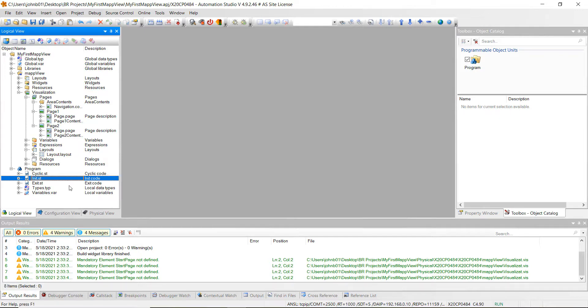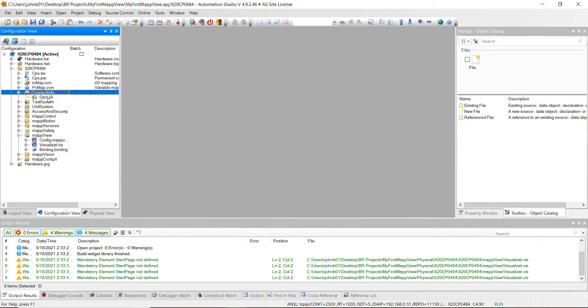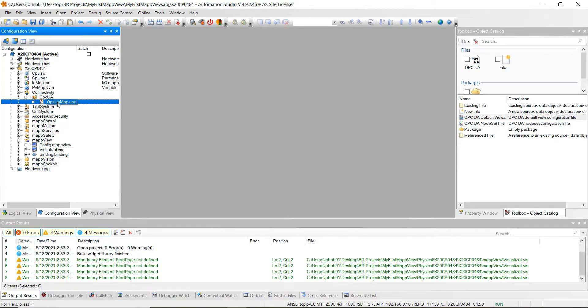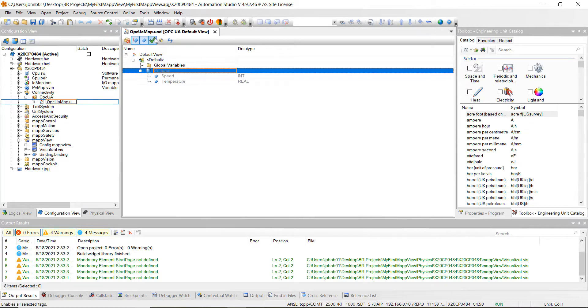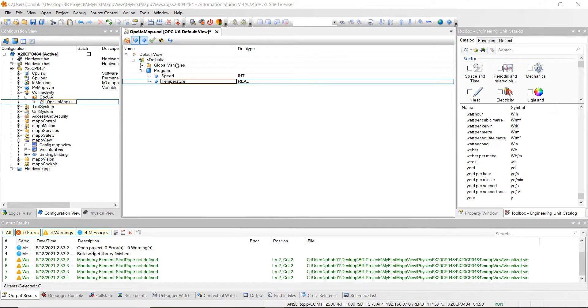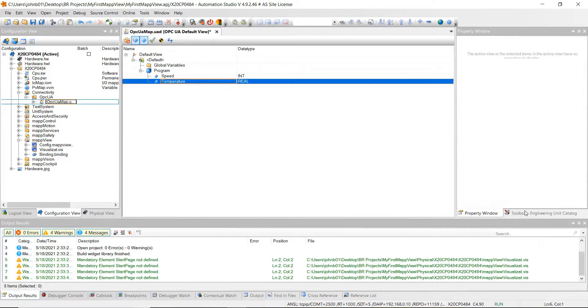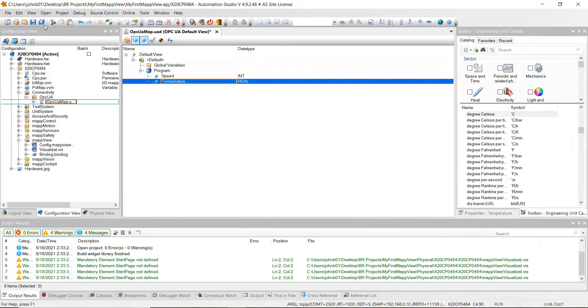We created the program with the variables we want to use for our visualization. Next, let's go to the configuration view, then connectivity, and highlight over OPC UA. We're going to add this OPC UA default view - just double click on it to open it up. Then double click to open it, and we want to enable this tag. Enable speed and enable temperature. For temperature, go over to the toolbox while you're over temperature and we want to put this as degrees Celsius. Double click on that and then hit save all and close out of there.